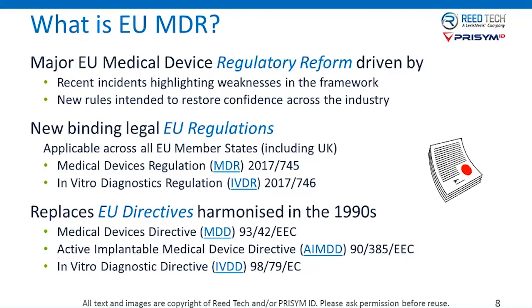So it's actually going to be necessary for manufacturers to complete somewhat of a gap analysis of the requirements of the EU over what they've implemented for other regulatory authorities such as the FDA. And that's part of what we're also highlighting here, is how you can use what you've already done for the FDA to help you move forward with EU MDR.